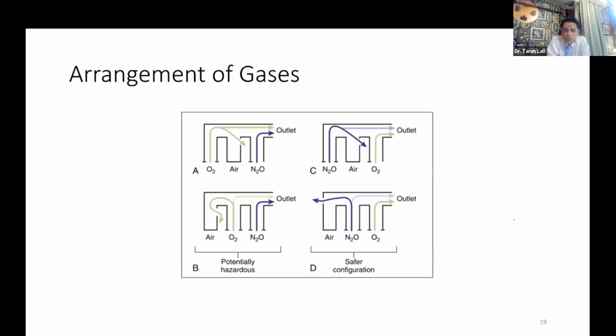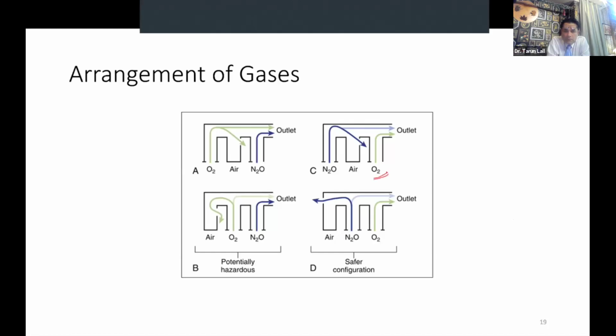Now, again, one question that is commonly asked, and is important for all of us from the safety point of view, is how the flow meters are arranged on the anesthesia machine. This is a diagram from Miller's, which shows three or four different types of arrangements of the flow meters. What we must always remember is that oxygen should always be the last gas that is added to the circuit. So oxygen should be downstream.